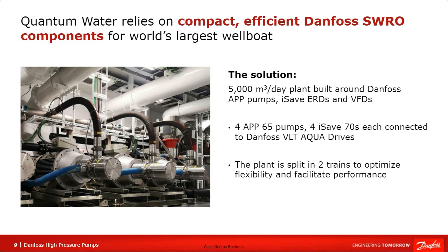What has been installed on board: our customer Quantum designed and manufactured a 5,000 cubic meters per day plant made with Danfoss high-pressure pumps, energy recovery devices, and drives. The plant is made with four high-pressure pumps — four APP 65 — and four energy recovery devices, the iSave. The plant is divided into two trains to facilitate performance.